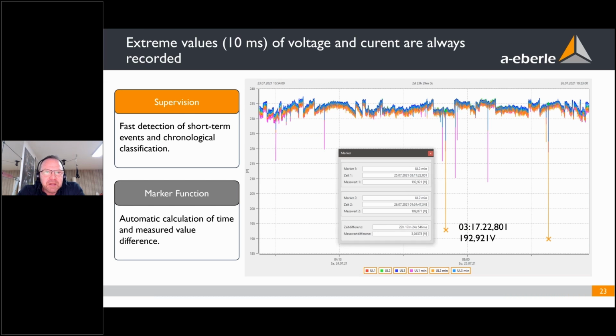If you make a long-time measurement, there's also a big feature in our software. Even if you measure for months, if you click with a cursor on the extreme values, voltage dips, swells, current peaks, you get information exact to 1 millisecond. Here is a voltage dip to 192 volt, and even if you have long-time data with a 10-minute interval, the software tells you when the dip occurred, down to the millisecond. So the timestamp is exact to 2 milliseconds for each data point, even if you are analyzing only the online data.